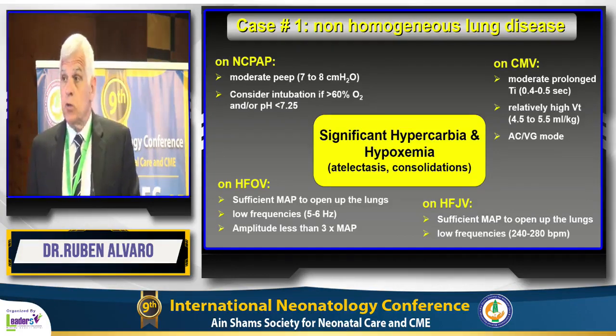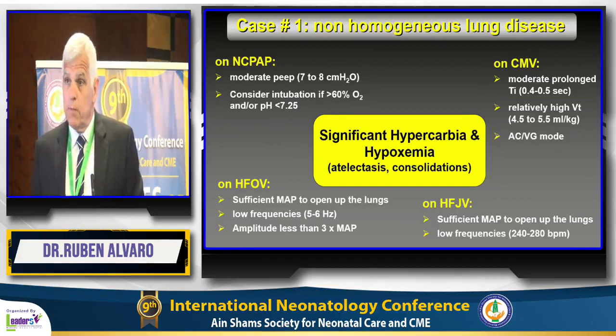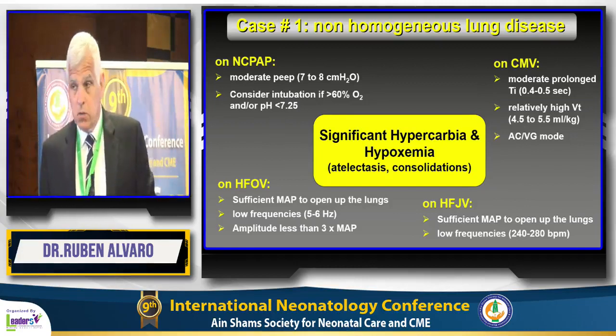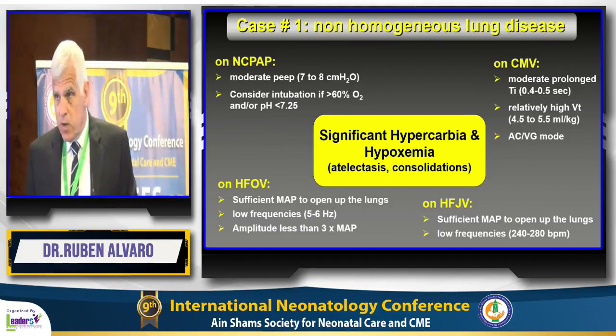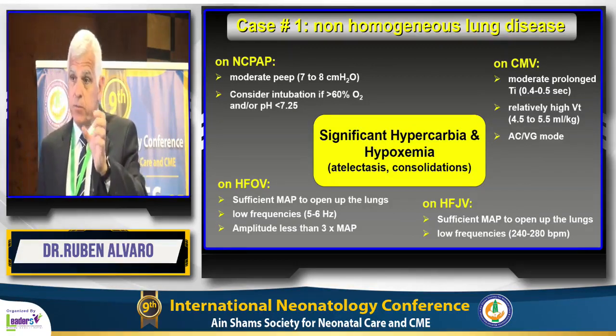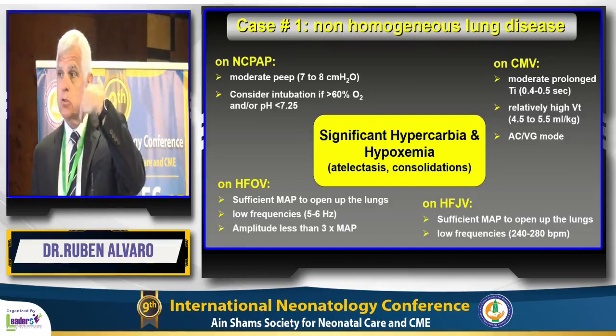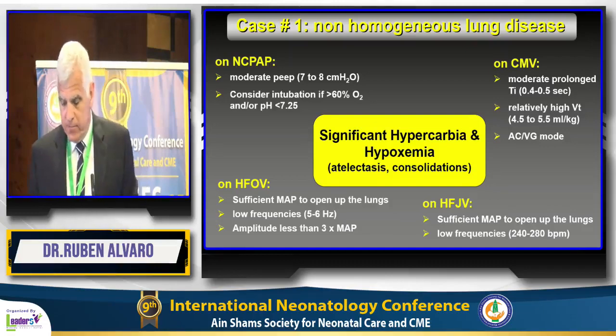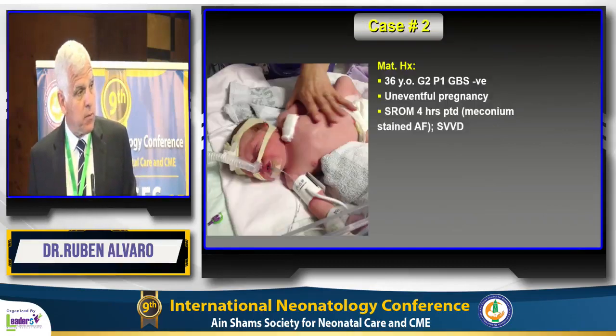Frequencies, again, should be low, no more than 240 to 280, for the same reason as on the oscillator: there's a risk of air trapping, so you need to slow down. You need enough time for expiration to allow the lungs to be completely empty after each breath. Otherwise, you end up with air trapping.